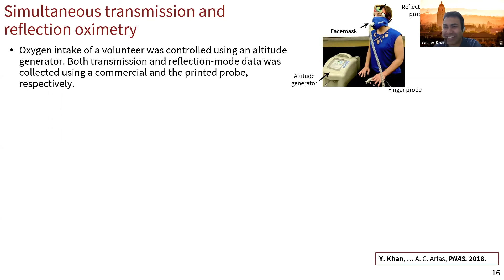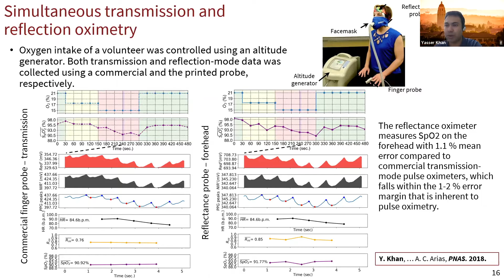It was hard to get an IRB, but we tried that. And so this is the result, where here you can see the first panel. So normally we breathe 21% of oxygen. And then with this machine, we can reduce it down to 17.5 and then 15 and see what's the response in SpO2. And we put one commercial probe on the finger and one reflection mode probe on the forehead. And here you can see the SpO2 level tracks really well for both the devices, even if you change the oxygenation. So that was really good. It's essentially validated that with lower oxygenation, we can use our device.